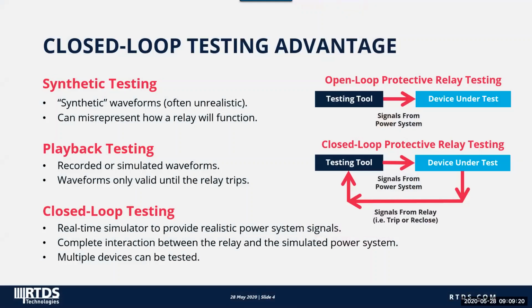Testing protection and control devices are generally divided into two categories: open loop testing and closed loop testing. Compared to open loop testing, closed loop testing has the advantage of providing the complete interactions between the device under test and the simulated power system. It is the ideal approach to fully study a target power system involving single or multiple physical protection and control devices, and to better validate the protection control functions of the devices in the integrated environment. Now, to achieve such closed loop testing, a real-time simulator that is capable of providing realistic power system signals and supporting required communication protocols is needed.